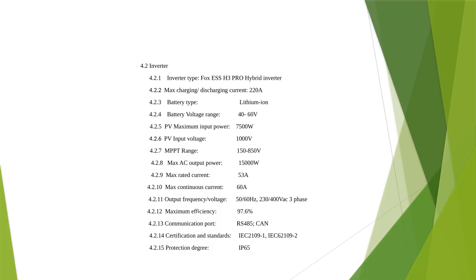Then the output frequency and voltage is 50 or 60 hertz, 230 or 400 volts AC 3-phase, at an efficiency of 97.6%, and the communication port RS-485 or CAN, and certification and standards should be it should comply with IEC 62109-1 and IEC 62109-2, and the protection degree is going to be IP65.